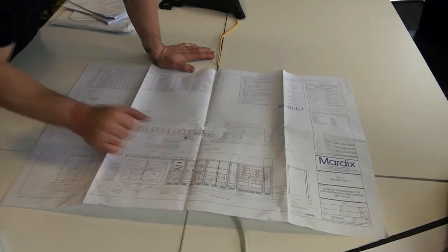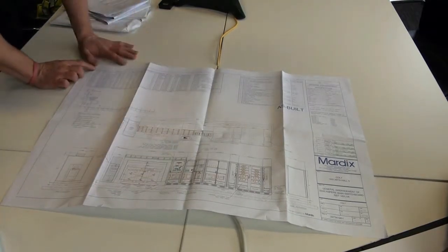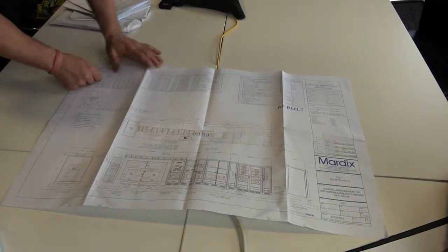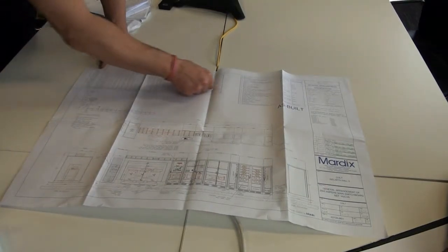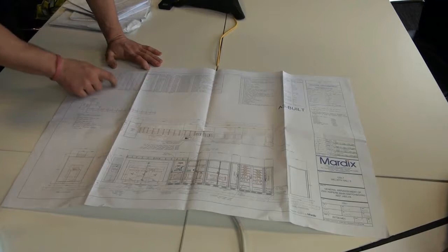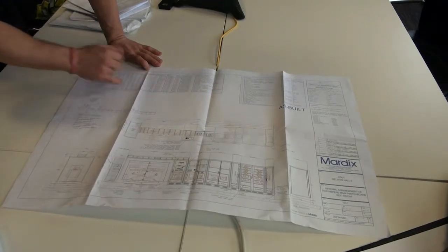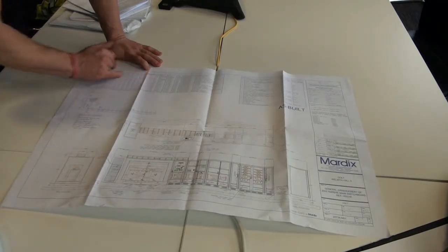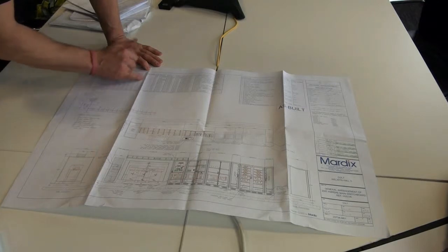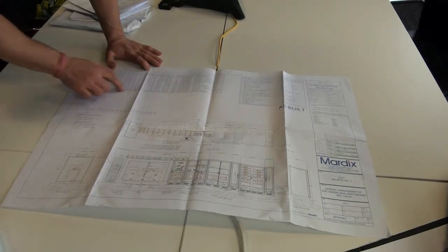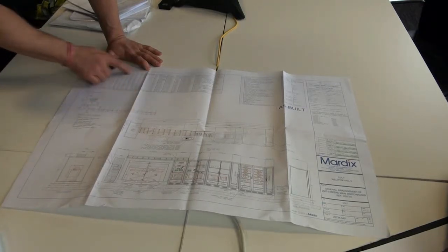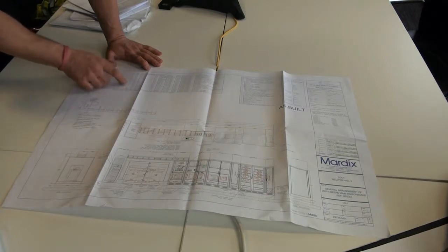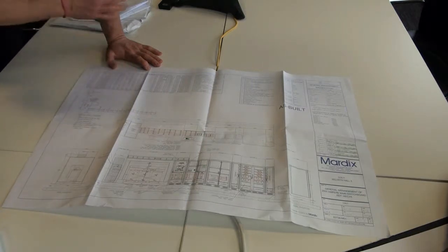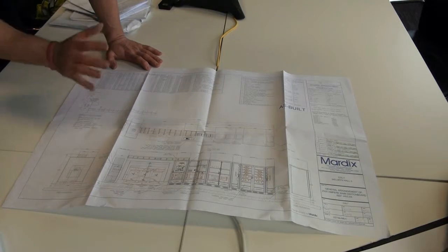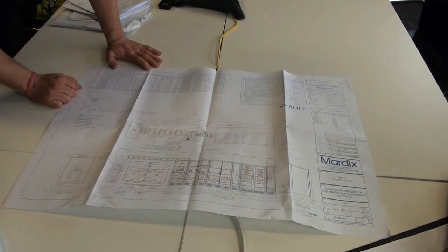That's breaker A1, mains incomer. If you follow that A1 to your references up here, you've got a complete listing of what it should be. This information is given to us by the consultants, i.e. the Micrologic trip unit settings. It's got all of them listed there. That might differ because someone at some point might have come in and changed it, so don't look at that and think, oh, that's different, that's an alarm. It's not. It could be that it's been changed at a later date.